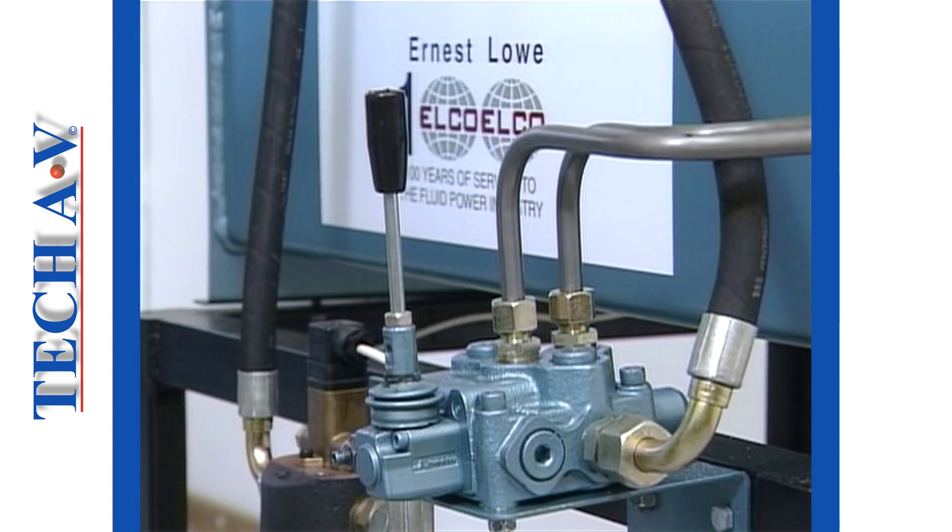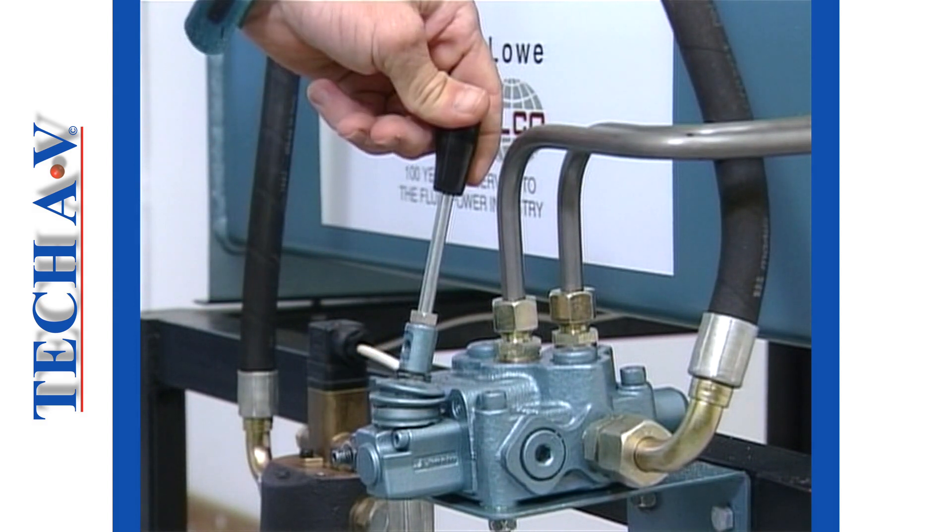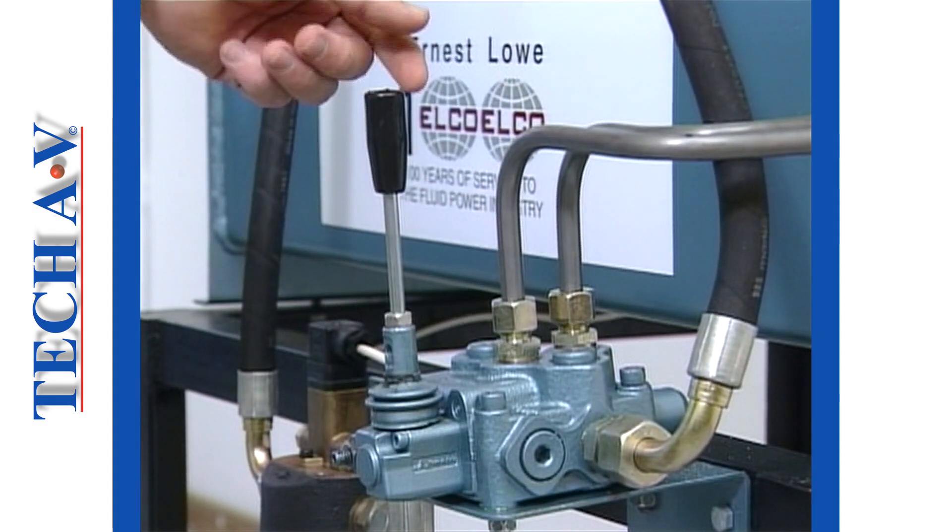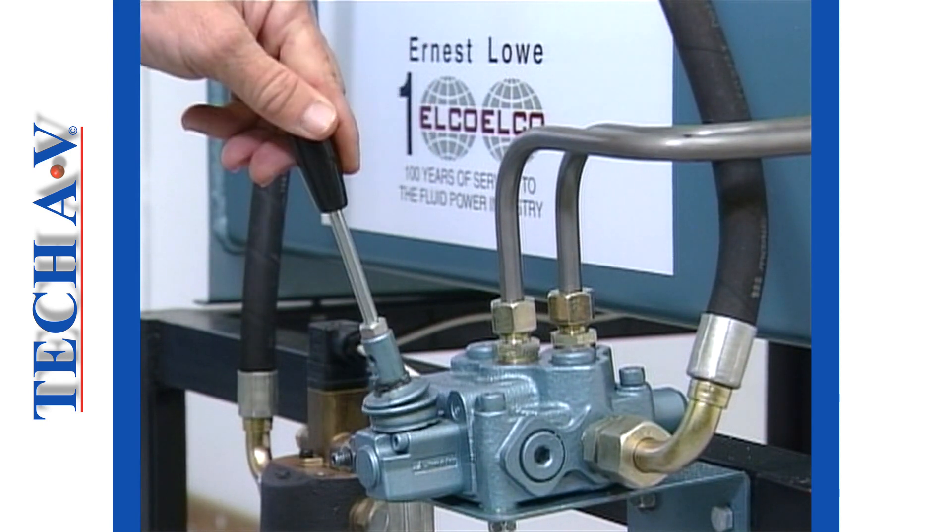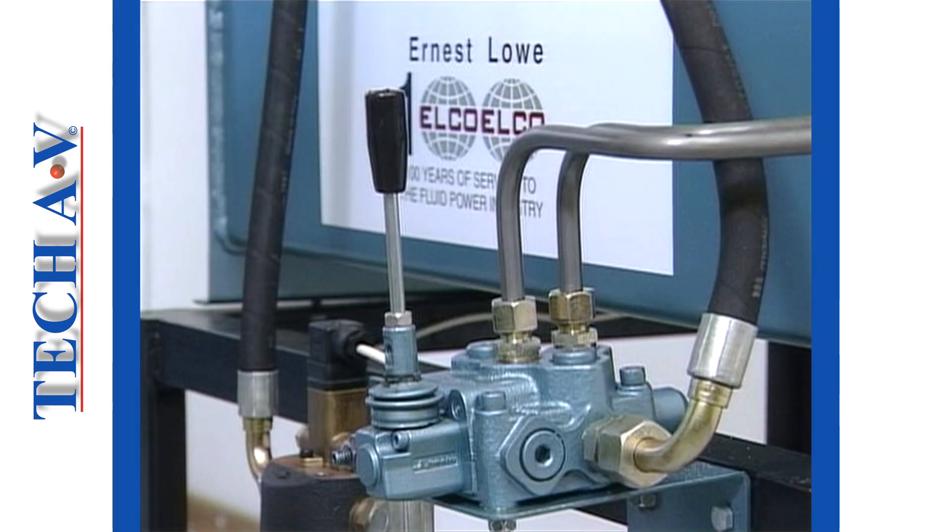Two other features are that the valve is manually operated with a control lever, and the lever returns automatically to the center position by spring action. This symbol depicts a manual lever. A spring symbol at each end of the spool indicates that the spool is spring-centered. The center position is the normal position for this valve.